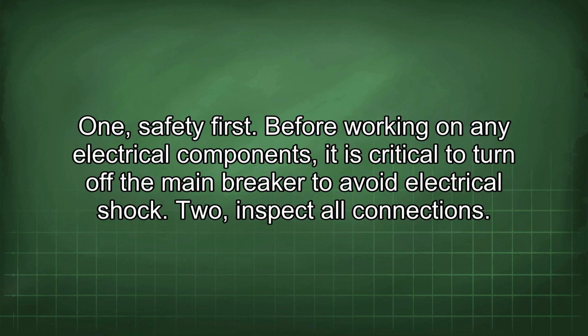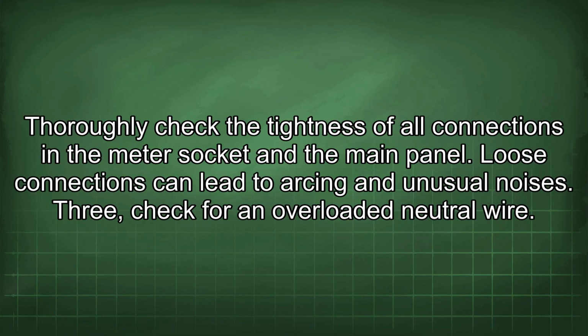1. Safety first. Before working on any electrical components, it is critical to turn off the main breaker to avoid electrical shock. 2. Inspect all connections. Thoroughly check the tightness of all connections in the meter socket and the main panel. Loose connections can lead to arcing and unusual noises. 3. Check for an overloaded neutral wire.